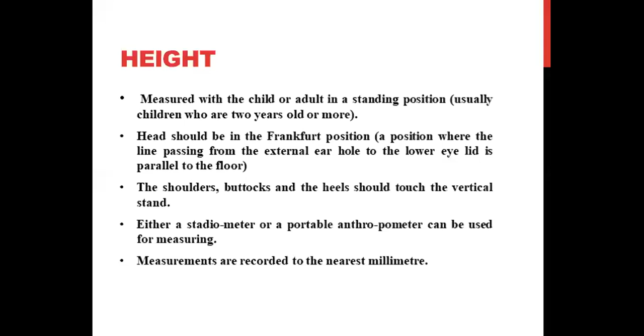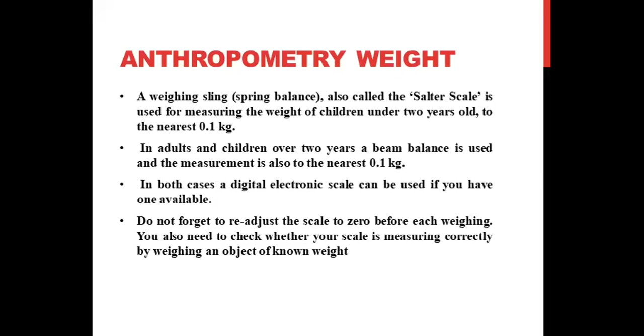Anthropometric weight. A weighing sling or spring balance, also called a Salter scale, is used for measuring the weight of children under 2 years old to the nearest 0.1 kg. In adults and children over 2 years, a beam balance is used and the measurement is also to the nearest 0.1 kilogram. In both cases, a digital electronic scale can also be used if you have one available. Don't forget to readjust the scale to 0 before each weighing. You also need to check whether your scale is measuring correctly by weighing any object of known weight. Various electronic machines can be used for weight measurement.